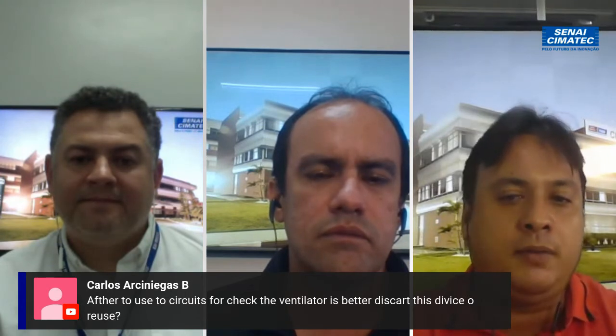The breathing circuit is commonly sent to the sterilization center of the hospital, where it is cleaned, disinfected, and sterilized, and then put on the patient again. If you use the breathing circuits only for testing equipment, not on patients, you can use the same circuits many times without cleaning. But if you use them on patients, it's mandatory to follow the cleaning, disinfection, and sterilization process determined by the manufacturer and the infection control center in the hospital. Okay, great. Thank you. Okay, go ahead, Rodrigo.